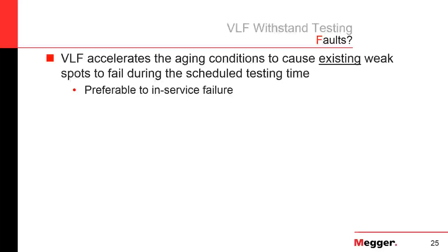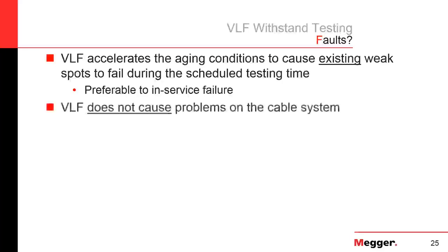It also, because of the power involved in a VLF test set, it's much lower than the power available from a substation, so your collateral damage is also a lot less too. It's very often that a VLF test would fail and you only have to splice one phase. Well, if it failed in service, you may have to splice all three phases because of the damage to the adjacent phases.